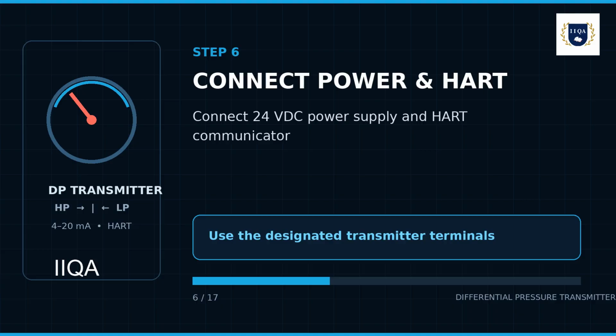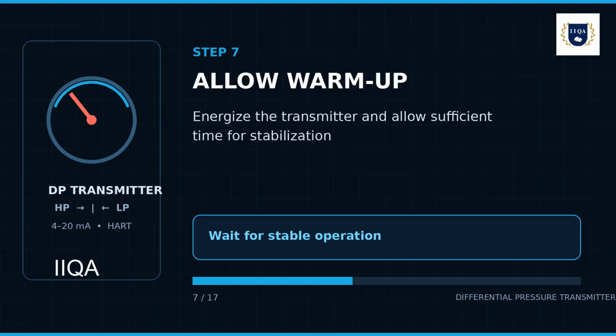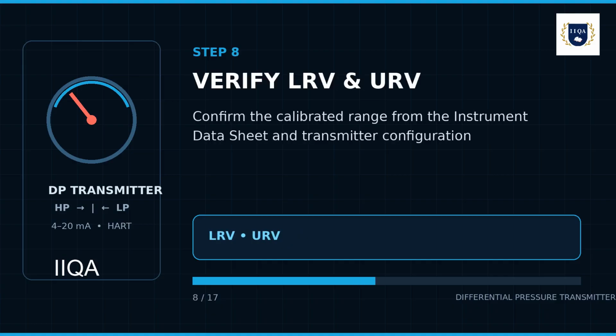9. Apply pressure equivalent to the lower range value, LRV. The transmitter output should indicate 4.00 milliamps, 0%. If necessary, perform a zero adjustment using the HART communicator.